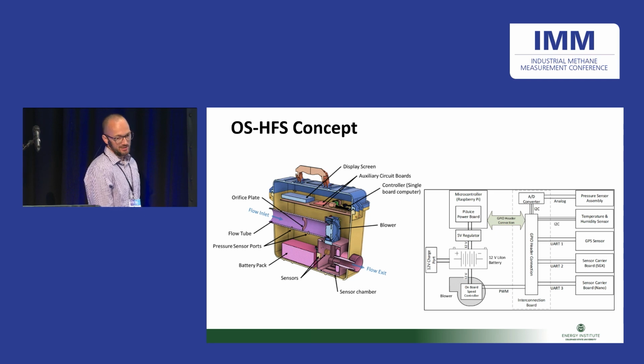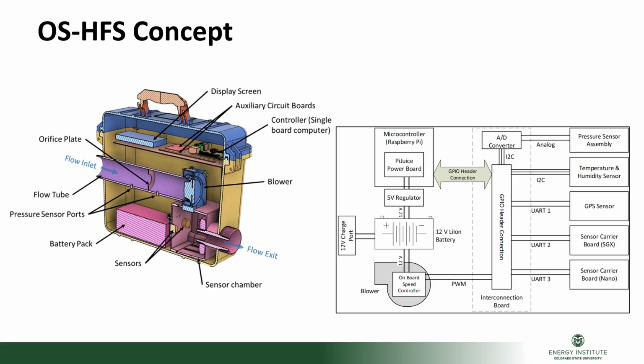So we've got a Pelican case here. We've got our flow inlet and then our orifice plate flow meter. We've got our pressure sensor port taps and our blower there, our battery, our sensor chamber with our sensors in it, and our flow exit.